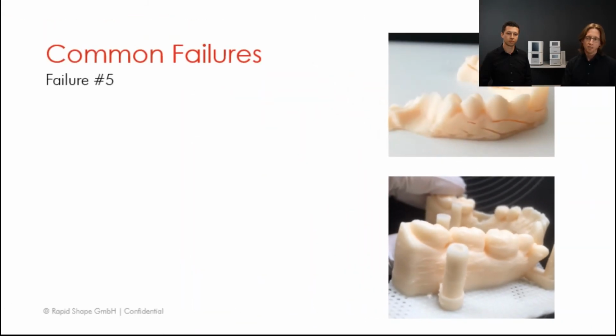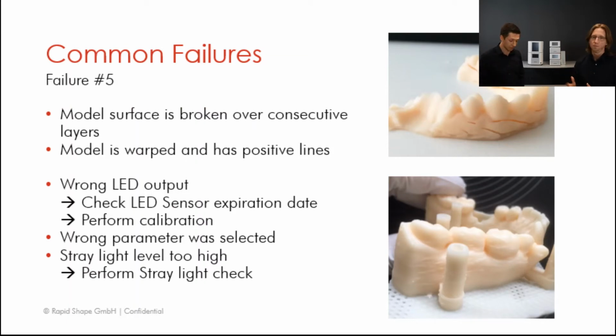All these two pictures we see here are related to energy. Energy is a problem we can solve by calibrating the machine. Robin mentioned that earlier. It's all about the weekly maintenance and doing the auto calibration. Basically, we just want to check, was the calibration performed on a weekly basis? Could be the customer forgot about this, or maybe the LED sensor expired? As you all know, there's an expiration date on the LED sensors. This is a year from delivery, which means after a year, the sensor must be shipped back to Rapid Shape for recalibration, to ensure that the sensor is working in the correct range of power output.